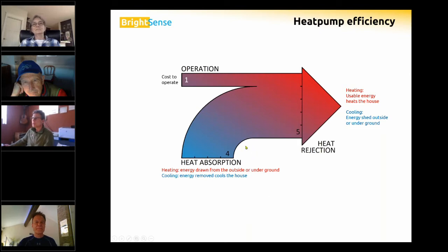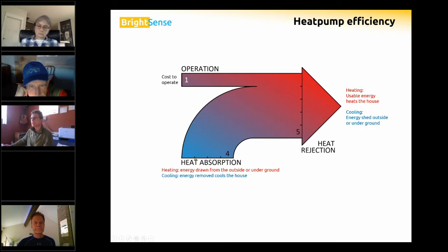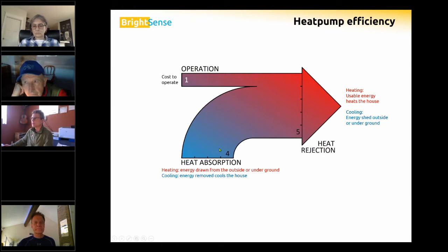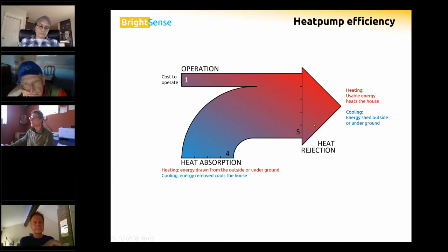Let's look at the energy balance. Here at the bottom, if we are absorbing four units of energy outside, our heat pump sits outside absorbing thermal energy. Using four units as the example, and assuming we spend one unit of energy to run the compressor, four plus one gives us five units of usable energy to heat our house or heat the water.